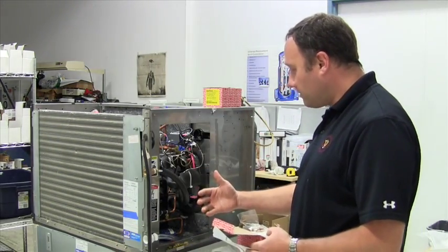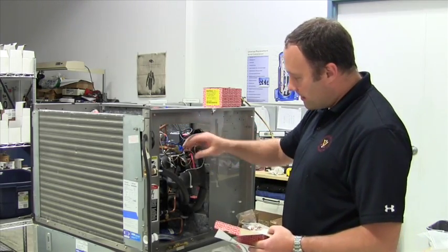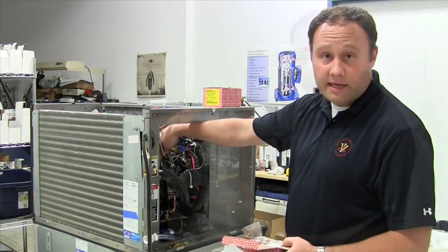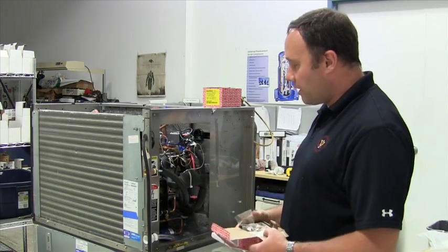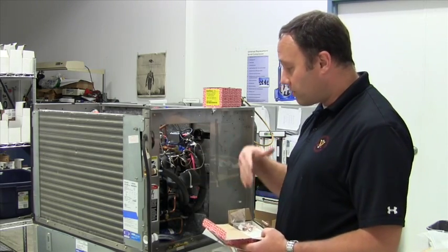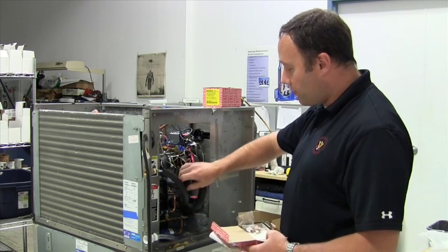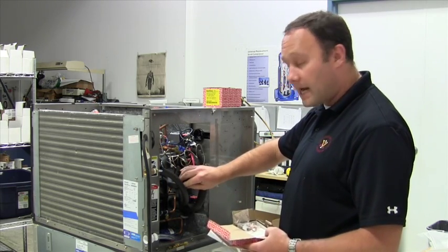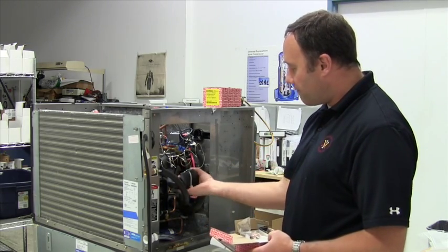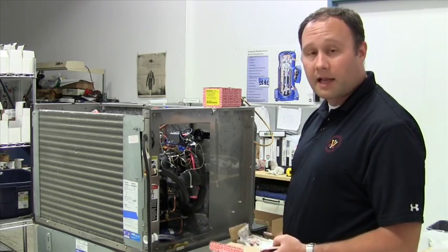With the side panel of the ice machine open, we can identify the capillary tube, see where the TXV is sitting, and where the bulb is located. First we need to do prep work: pull all of the refrigerant — recover and reclaim it out of the system — then pull the insulation off of the thermostatic expansion valve. After recovering the refrigerant and removing the insulation, we're ready to start the installation of the new kit.